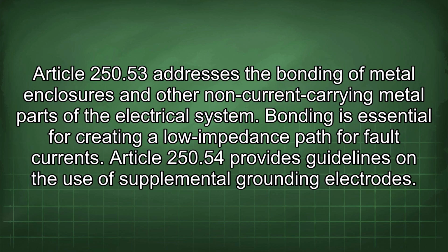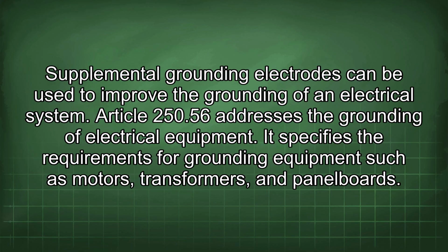Article 250.53 addresses the bonding of metal enclosures and other non-current carrying metal parts of the electrical system. Bonding is essential for creating a low impedance path for fault currents. Article 250.54 provides guidelines on the use of supplemental grounding electrodes. Supplemental grounding electrodes can be used to improve the grounding of an electrical system.